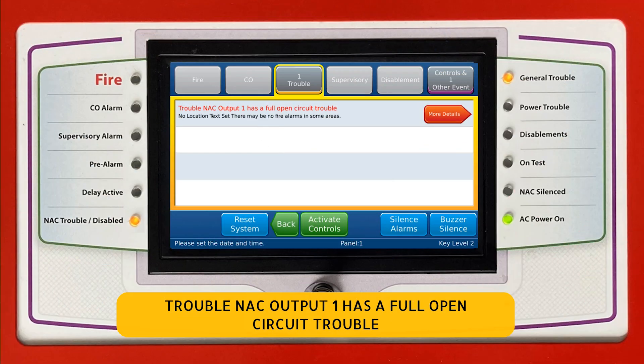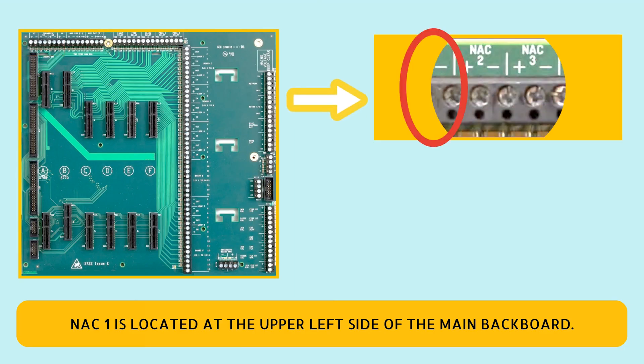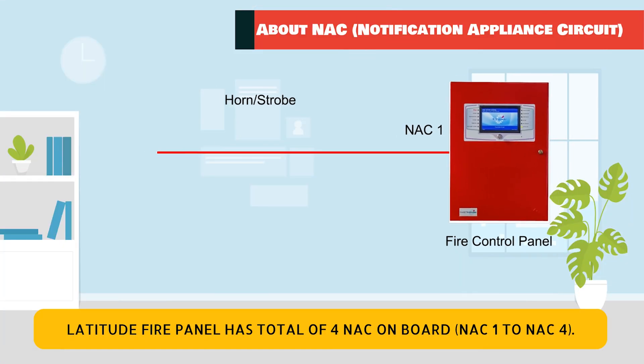The trouble reads: NAC output one has a full open circuit trouble. NAC1 is located at the upper left side of the main backboard. The Latitude fire panel has a total of four NACs on board — NAC1 to NAC4.